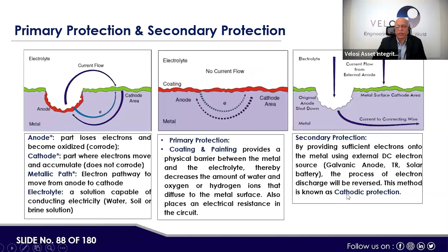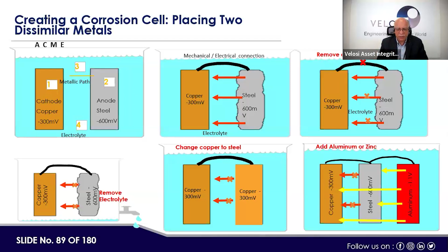So, from a definition point of view, creating a corrosion cell, placing two dissimilar metals, right? Like how we normally make this combination for cathodic protection, like a cathode copper, anode steel, or copper and steel. Various potential differences are there. We can make mechanical and electrical connections, remove connections, then what will be the scenario? Change copper to steel, what would be the scenario? Add aluminum or zinc, what would be the scenario? So there are various kinds of combinations which could be tried while designing the CP system.